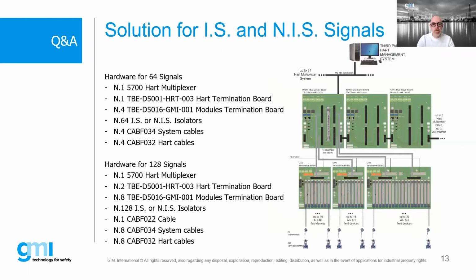And the system can be extended by inserting isolator or intrinsically safe barriers mounted on a DIN rail or on termination board in the loop, which then connect directly to the safety system through a dedicated system cable. As the slide shows, let's see how the insertion of barrier or isolator and termination board changes the loop. Do you want to add something on this topic, Andrea? Just an example for our customers. Also here, the example is only for single channel isolators. And for the dual channel, the architecture is a little bit different, and also the modules are different, but you can easily use single or dual channel, because our termination board can support both.